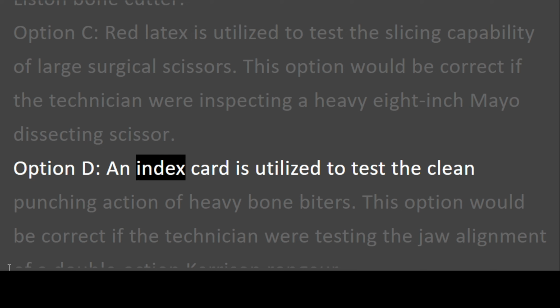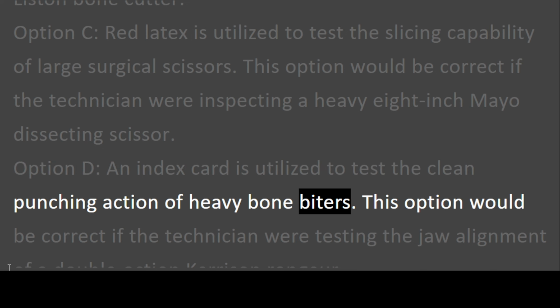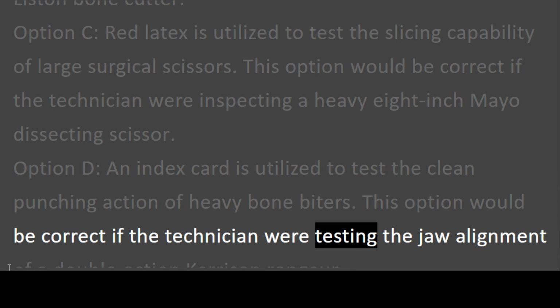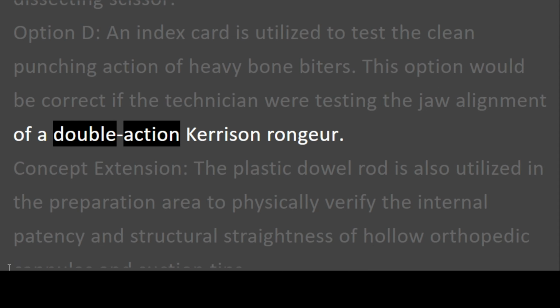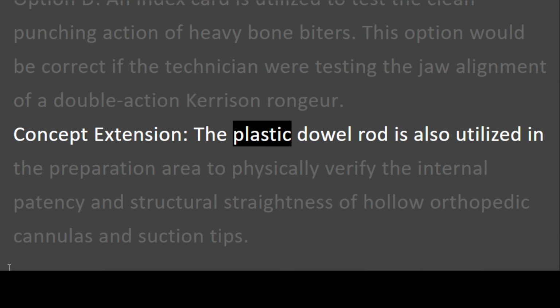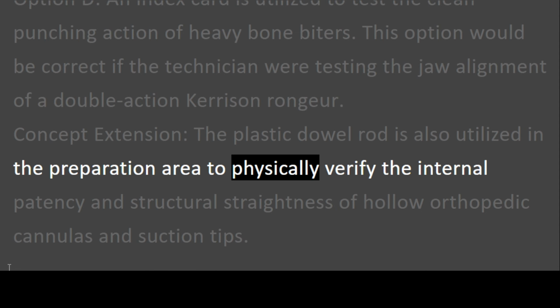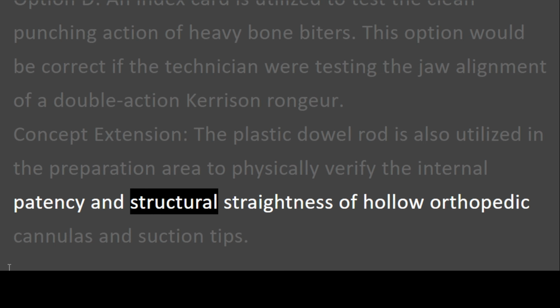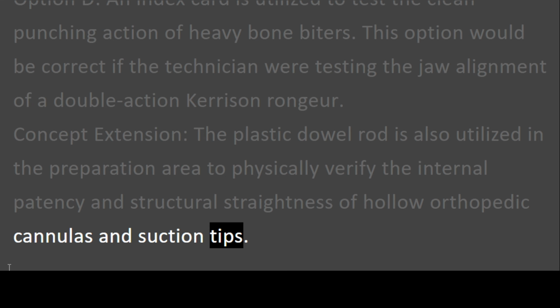Option D. An index card is utilized to test the clean punching action of heavy bone biters. This option would be correct if the technician were testing the jaw alignment of a double-action Kerrison rongeur. Concept extension. The plastic dowel rod is also utilized in the preparation area to physically verify the internal patency and structural straightness of hollow orthopedic cannulas and suction tips.